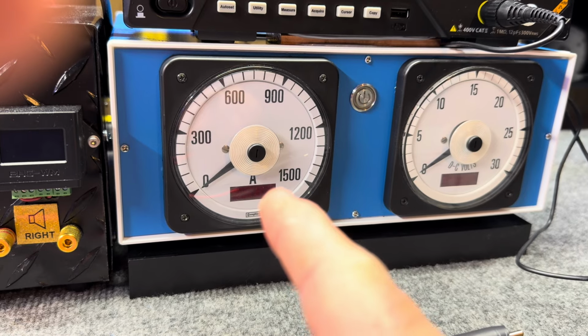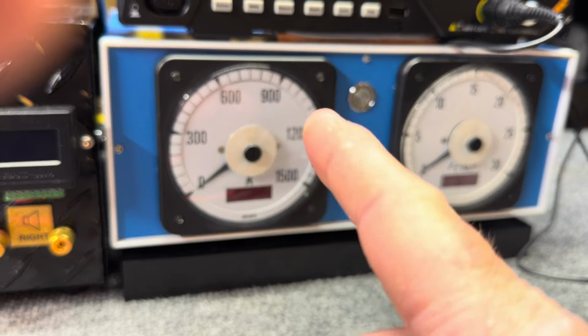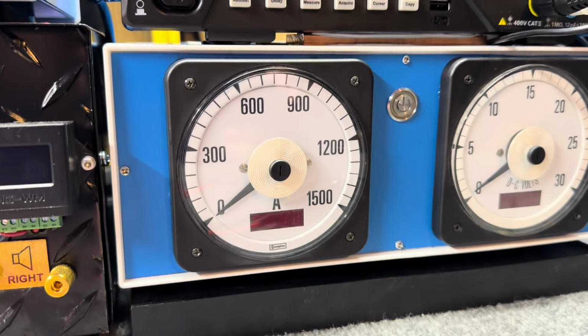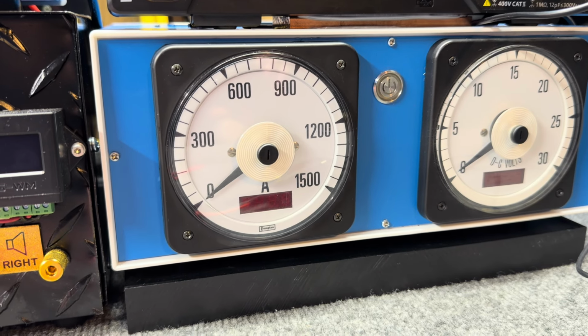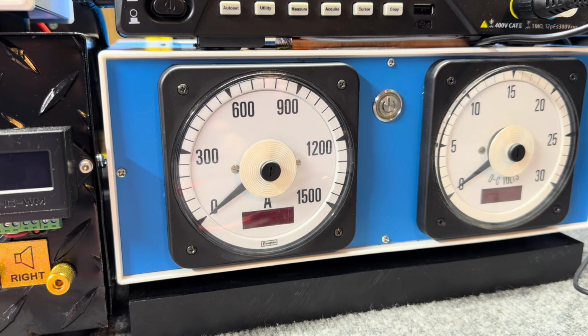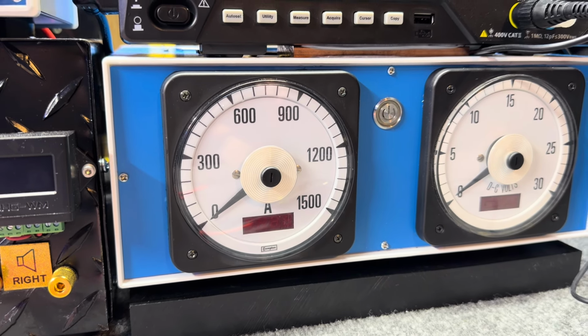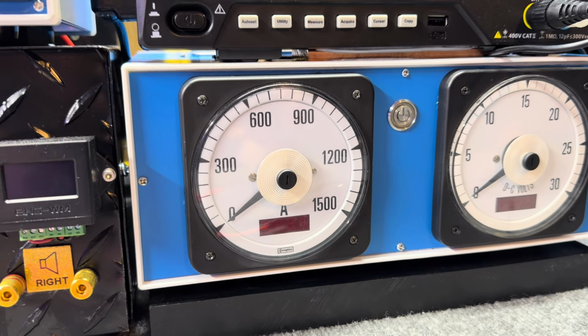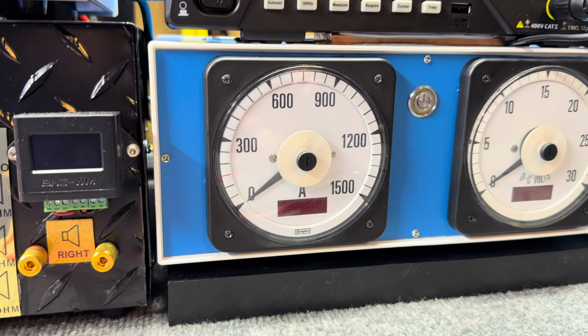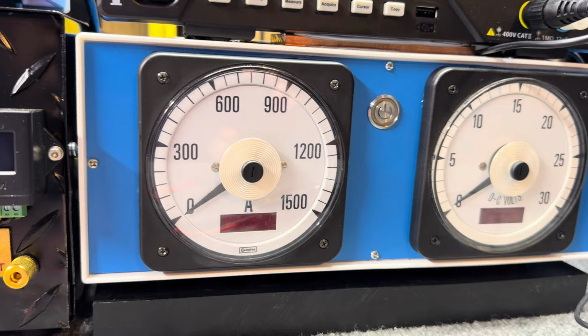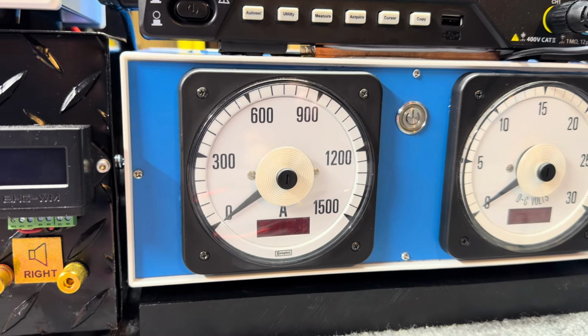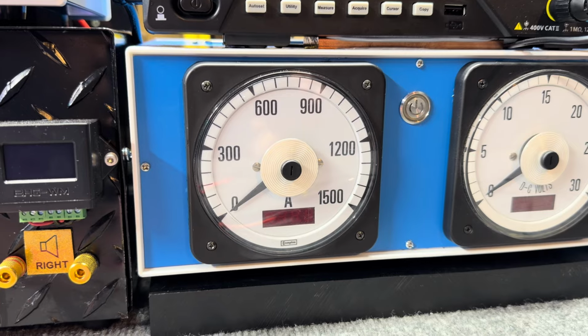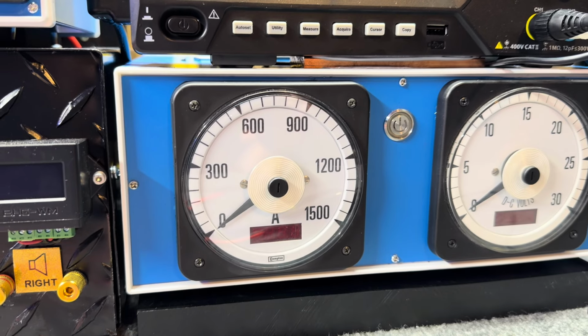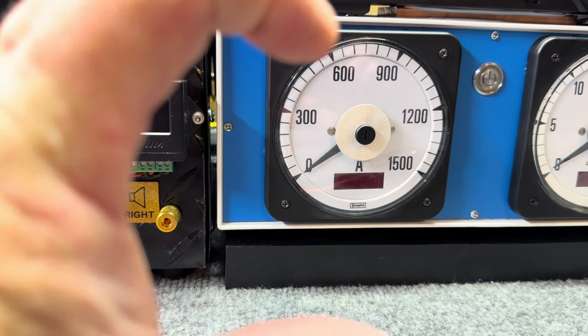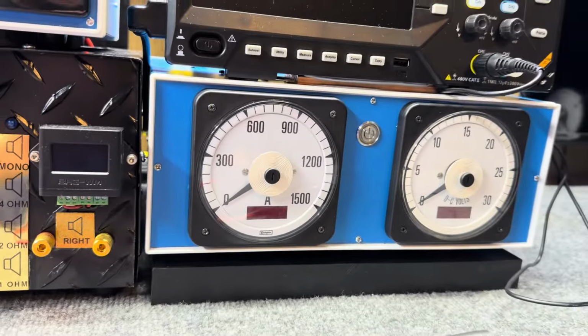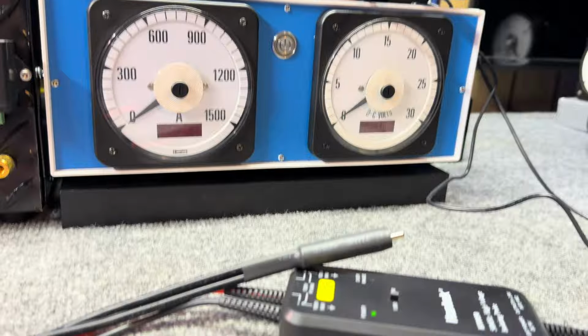Also, this thing samples kind of slow, so it takes a moment to register that current - not as fast as that Fluke clamp meter. I ordered a UNI-T 2000 amp AC/DC clamp meter - it's a cheap clamp meter, but UNI-T is actually a decent brand, and it's coming. Just to have a backup, because my Fluke only goes to 600 amps, and I'm sure if we do some big stuff it's going to max that little clamp meter out. I'm not paying through the nose for a Fluke that only does 1,000 amps - I think the biggest one I got does like 1,000. Like Big D's got the one with the detachable little face where you can read it remotely, that's all slick, but this is what I got, so this is what we use.